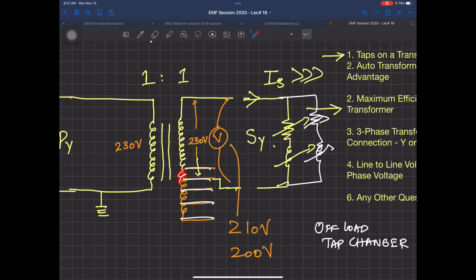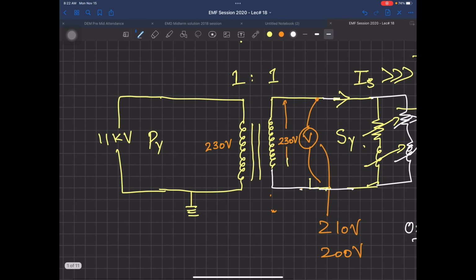This winding is expensive compared to the other one because of the thicker amount of copper. So practically they will not use taps on the LT side, and they will keep that side of the secondary the same. The taps are used on the high voltage side instead, here at taps 1, 2, 3, 4 and 5, because the current there is small. The copper is thin and cheap, so you can increase the number of taps on the HT side. This is common practice.